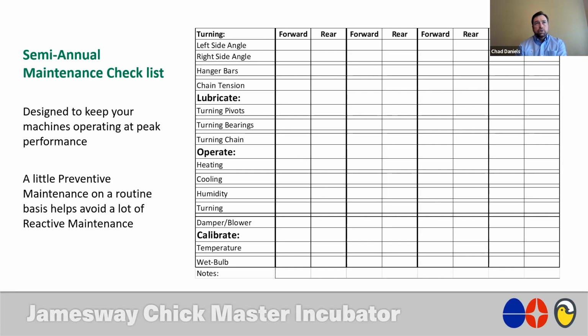And if you find an issue with something, let's just say, for instance, that we've performed this checklist on our first machine and we find that we have some issues with the condition of the fan blades. Well, what we want to do is focus on the process of getting that documented. Because if we don't continue on to the next machine and do documentation and all of these checks, then we'll get hung up at the first machine trying to fix all of these little issues. And so the reality of it is, develop your sheet, process through all of your machines, get things documented, pick out items that are similar or your biggest issue.